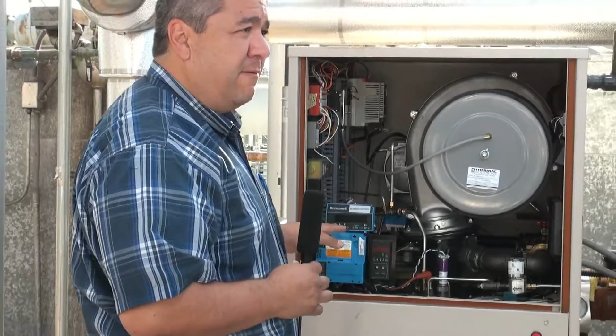Does the Honeywell controller have an hour meter? It does not have an hour meter, it has runtime. It has how many faults you've had. You go through the manual, it'll tell you all the things it does. They're very solid. They don't ever fail. I've never seen them fail. And most boilers that come out to installations don't even have this burner control module. This little controller actually comes out. You can take it off, and it doesn't affect the operation of your boiler. Only the operations of your Modbus, right?